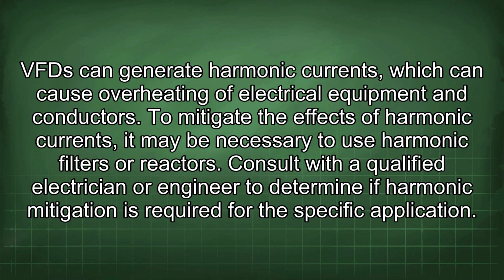VFDs can generate harmonic currents, which can cause overheating of electrical equipment and conductors. To mitigate the effects of harmonic currents, it may be necessary to use harmonic filters or reactors. Consult with a qualified electrician or engineer to determine if harmonic mitigation is required for the specific application.